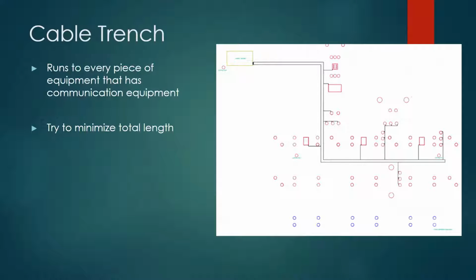This is our cable trench. It's going to run from our control house to any equipment that needs communications. So that would be transformers and breakers and things like that. That's for SCADA use, so supervisory control and data acquisition. That would allow us to open breakers remotely in case of faults or close breakers remotely in case of faults.